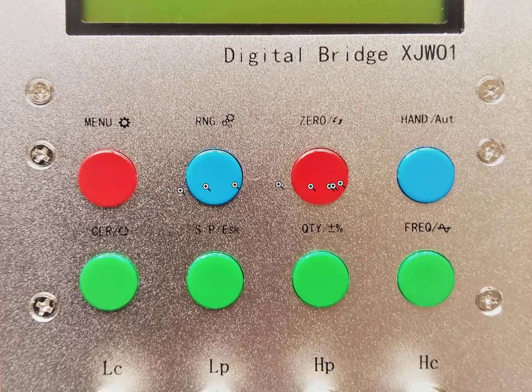So the main takeaways from this are that the hand button is for manual mode, switching between manual and auto mode. The 0 button is for your compensation of your probes, which you should do every time you switch it on or use it. CLR does not mean clear, it means capacitance, inductance, resistance. There should be a slash between each of those to make it clearer.